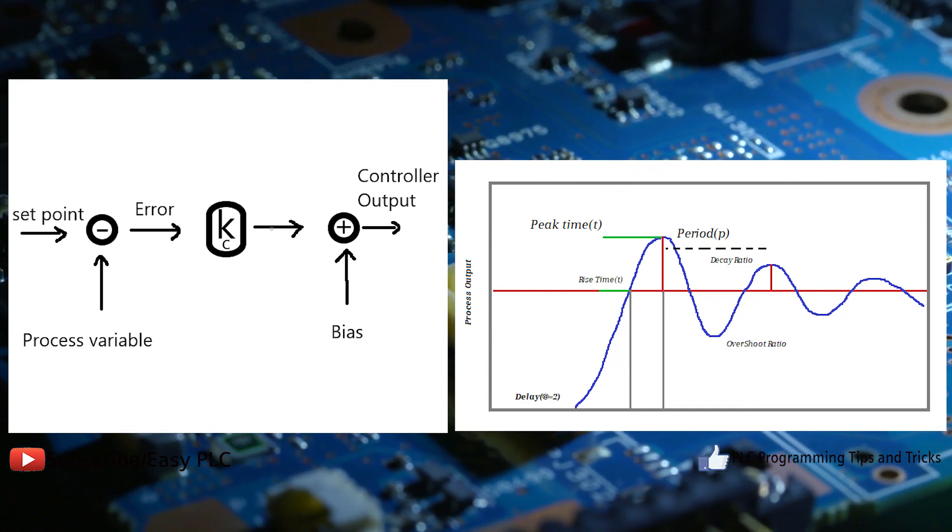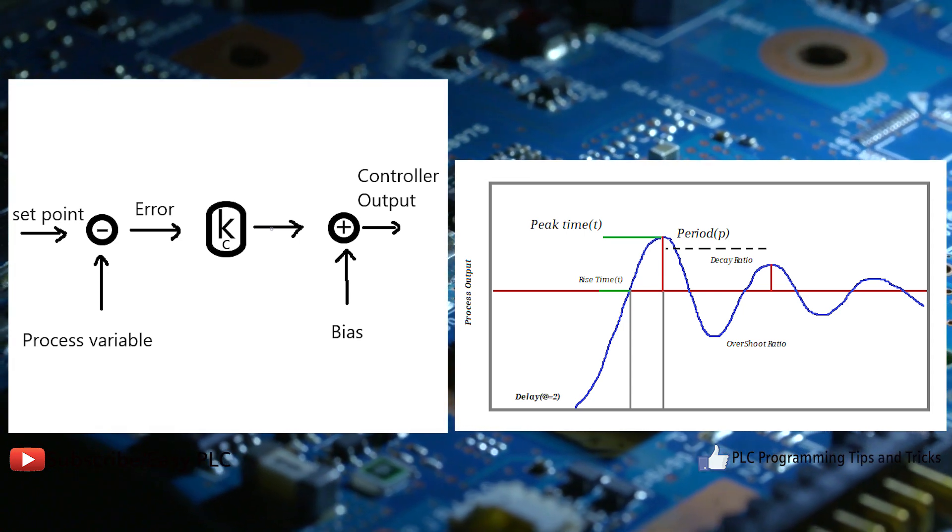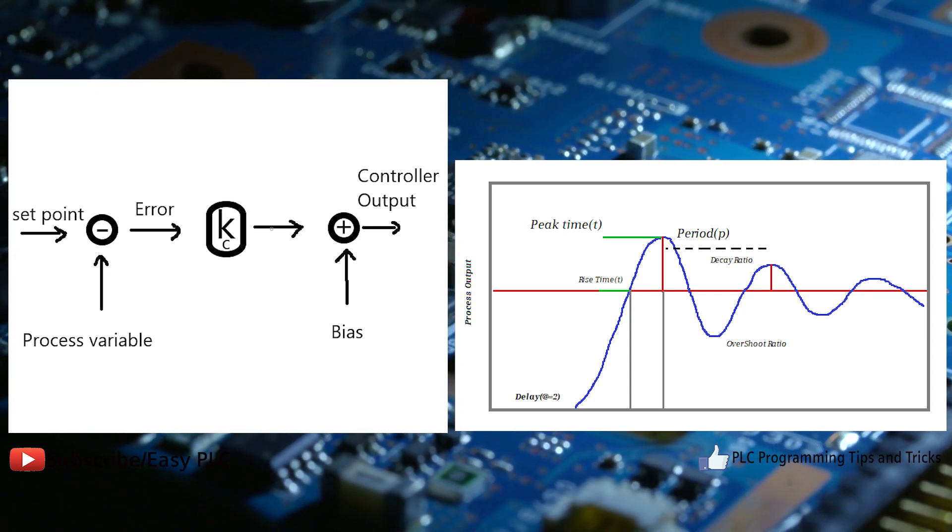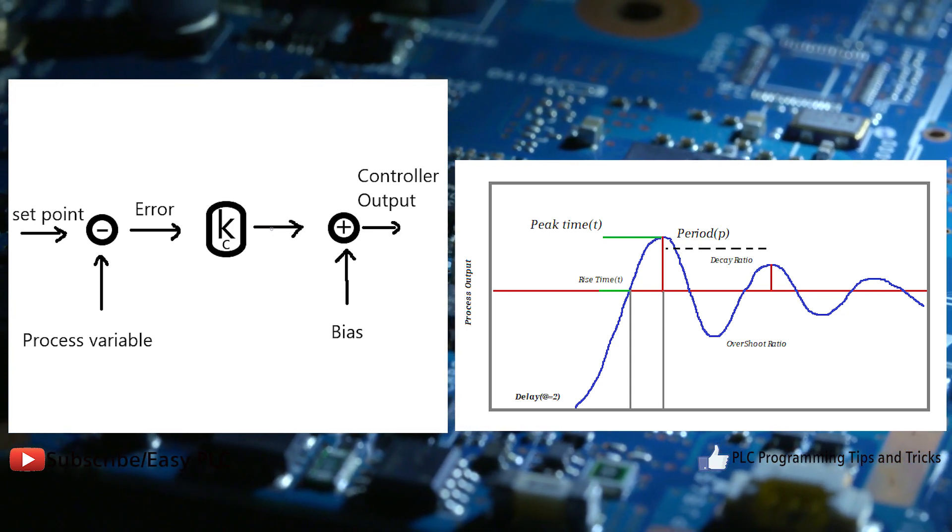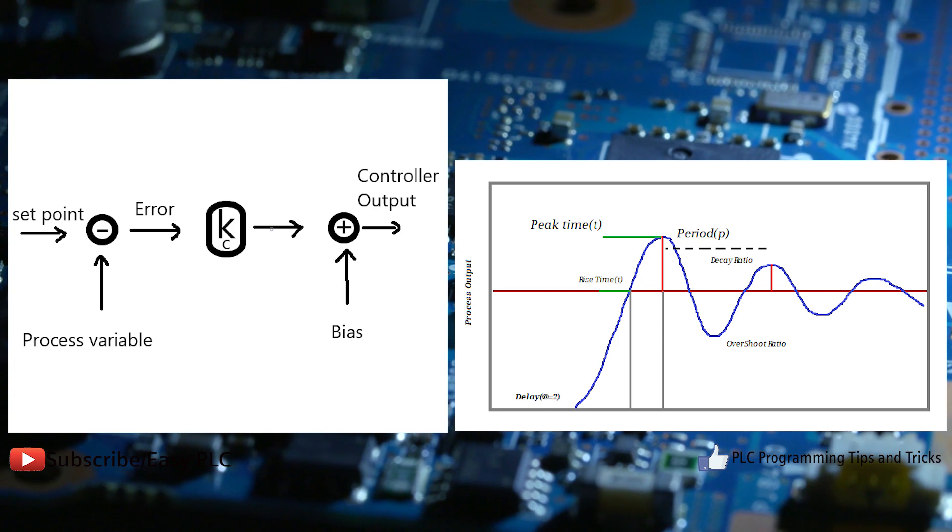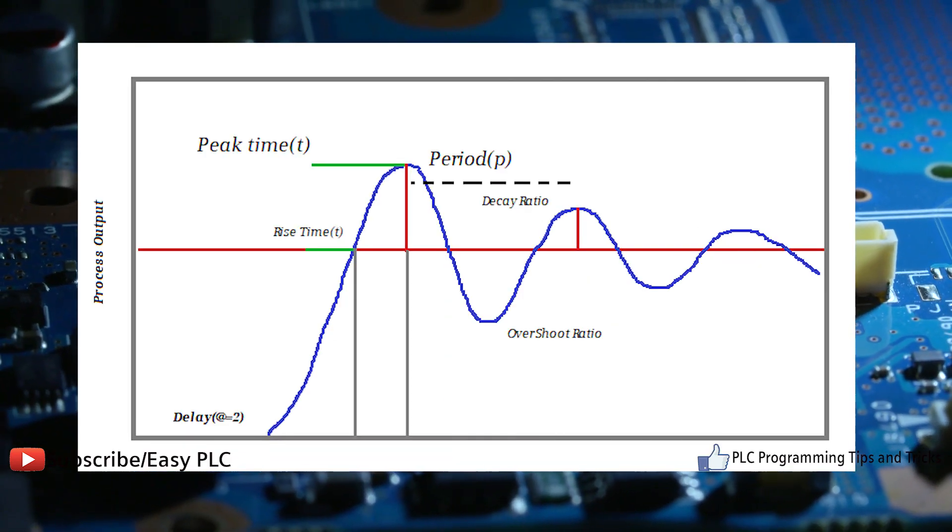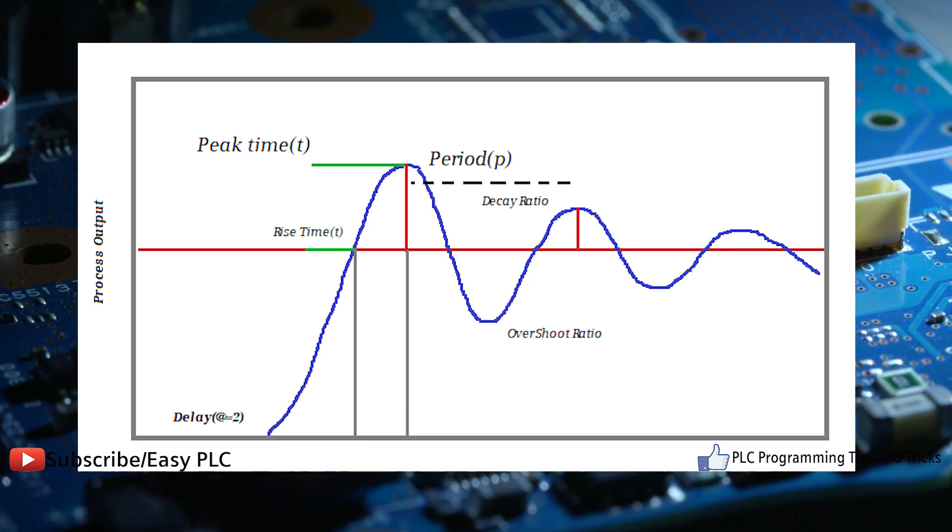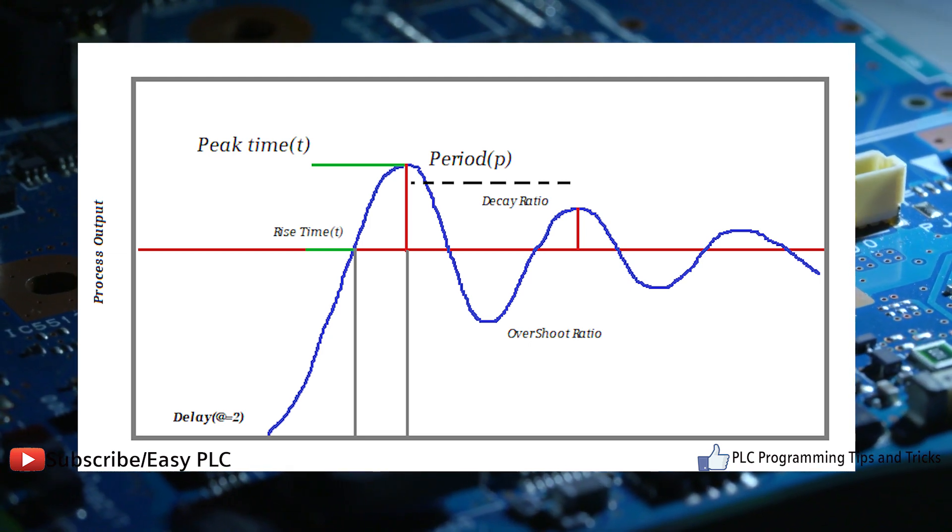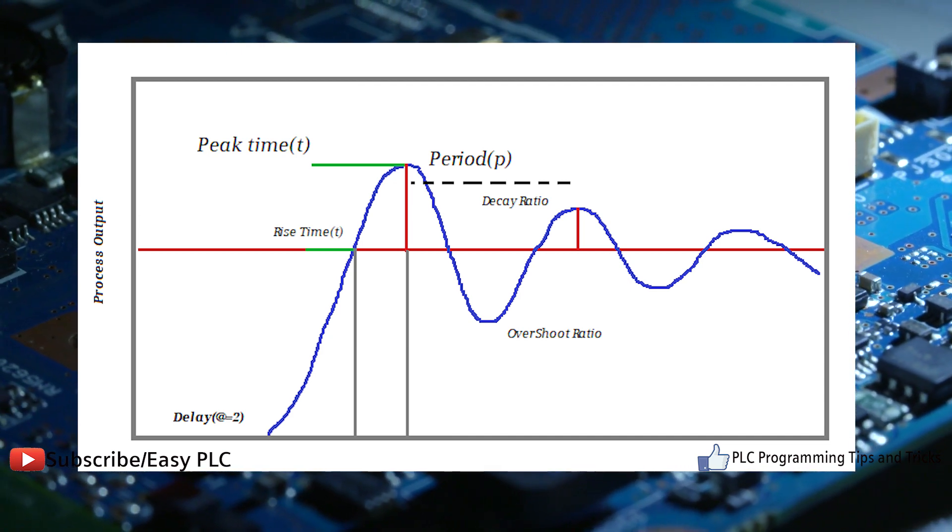P controller compares desired or setpoint with actual value or feedback process value. The resulting error is multiplied with proportional constant to get the output. If the error value is zero, then this controller output is zero. This controller requires biasing or manual reset when used alone.